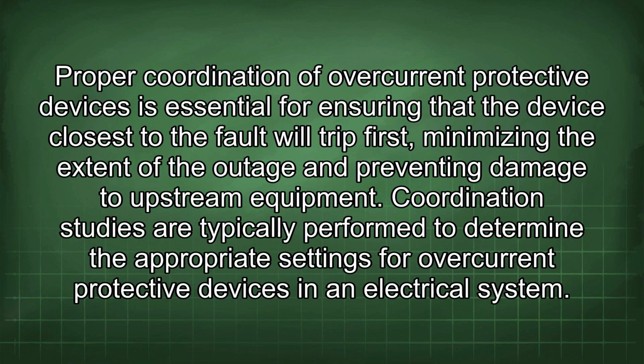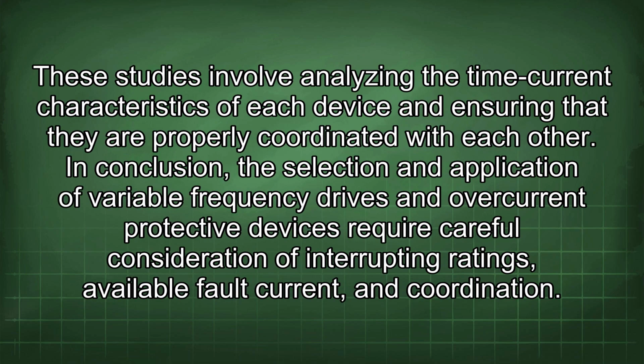Proper coordination of overcurrent protective devices is essential for ensuring that the device closest to the fault will trip first, minimizing the extent of the outage and preventing damage to upstream equipment. Coordination studies are typically performed to determine the appropriate settings for overcurrent protective devices in an electrical system. These studies involve analyzing the time current characteristics of each device and ensuring that they are properly coordinated with each other.